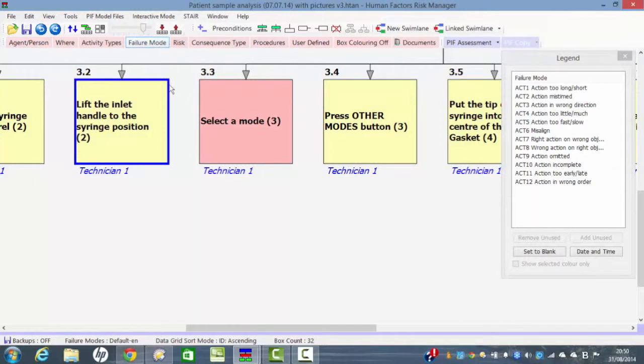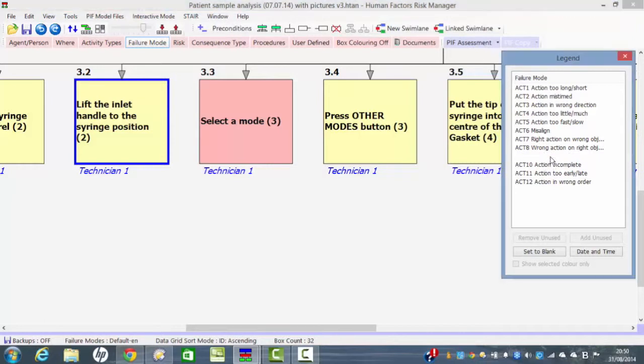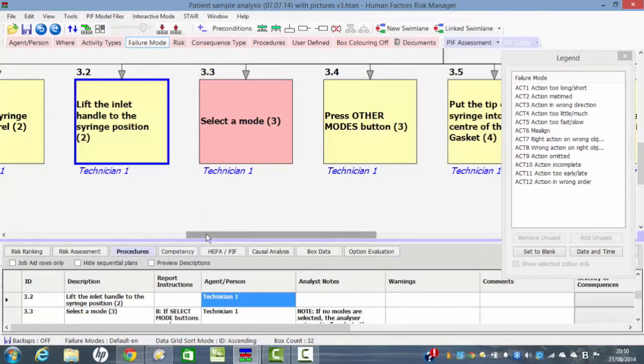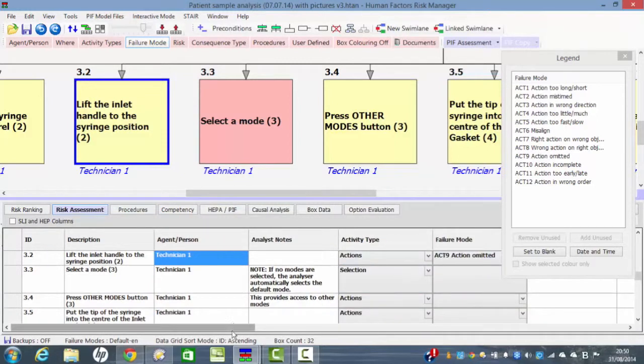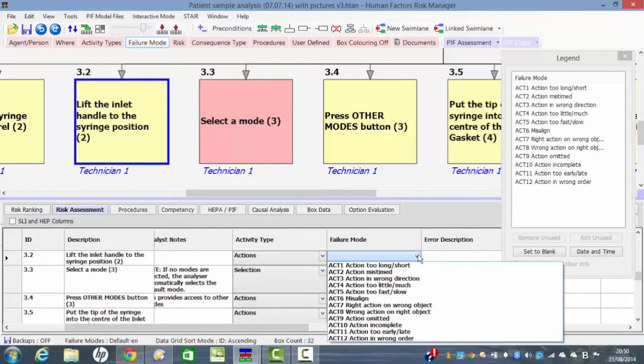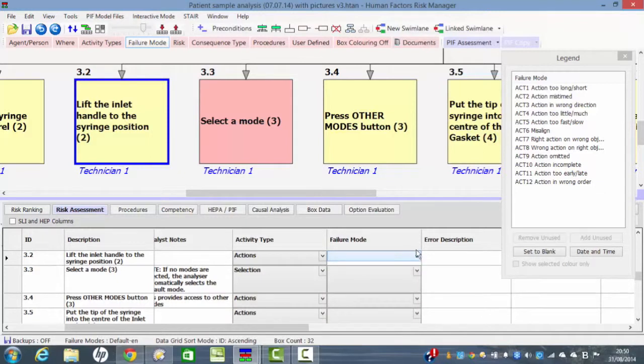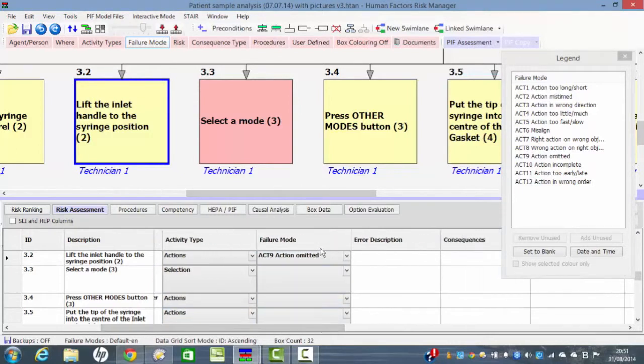So there's a number of techniques we have available for doing that but let's say that we think this step has a particularly significant outcome. So what we would do then is say okay this is an action what type of action could happen here. So we might omit to do this action. So if the action was omitted that information would then be entered into the table here. If I reproduce the table again, I go to that particular step which is step 3.2. We can see that we said that for step 3.2 the activity type is an action and the action could be omitted. So we've chosen from a list of significant failure modes which is the same as this list here.